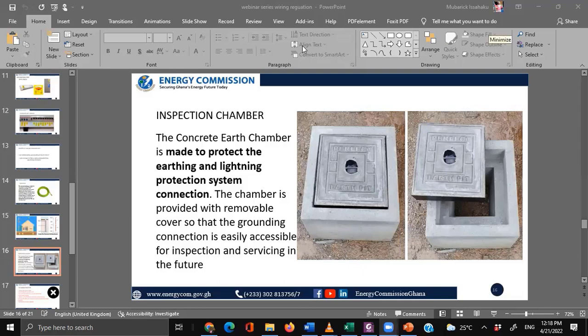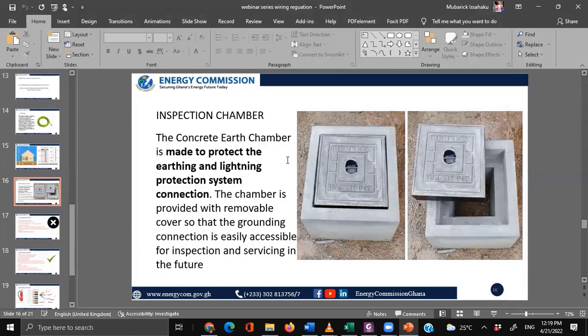So this provision is saying, if you are unable to get the 1 to 50 ohms and it's 100 ohms, you have to improve your earthing system. And the electricians have this know-how to improve the earthing system. They get earth enhancing materials which they pour in the pit there. So you see the open concrete you are seeing there, in order to improve the earth to the range 1 to 50, then you install your RCD. So the RCD moves hand in hand with the earthing system.